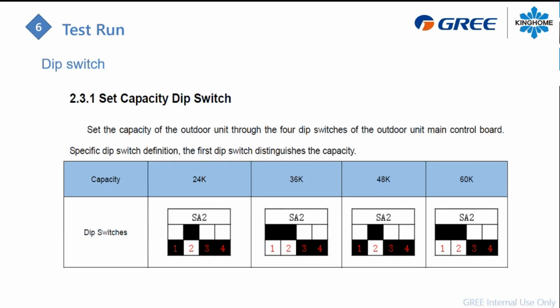In this outdoor unit, you will have some dip switches to configure regarding what kind of installation you did. For example, we call the unit a 3-ton or 5-ton, but it can be configured as a 2 or a 4, depending on which cabinet you're using. For a 3-ton unit, by default, it's configured as a 3-ton unit.